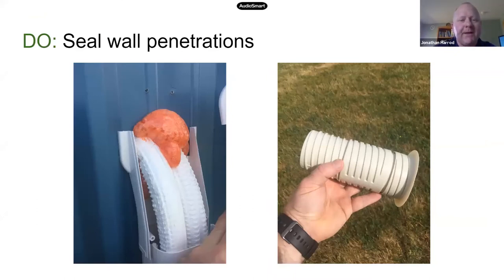So this is another really important thing that I think sometimes gets missed, which is properly sealing the places where the refrigerant piping and the control wires go through the house. Heat pumps move heat in and out of the house using refrigerant that travels through copper pipes. And there's also control wires that carry signals back and forth between the indoor and outdoor unit. So there's typically at least one, sometimes more, 3-inch holes drilled in the house. And if these aren't properly sealed, first of all, you'll get insects coming in. You'll get air leakage. If you're air conditioning, you can get hot, humid air that comes into the wall cavity. Condensation happens, and then you can get mold problems.